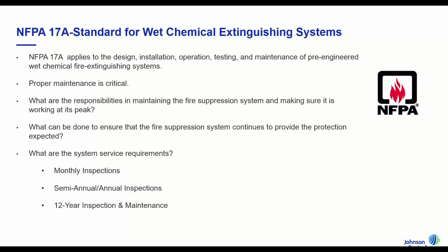The other standard relating more specifically to fire suppression would be NFPA 17A, which is the standard for wet chemical extinguishing systems. This standard specifically applies to the design, installation, operation, testing, and maintenance of pre-engineered wet chemical fire extinguishing systems.